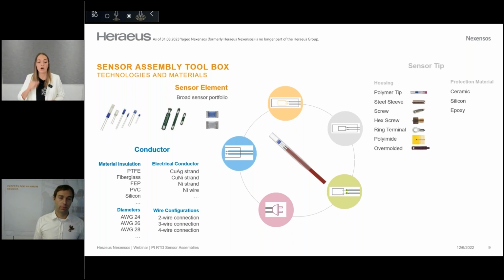Here you can see a selection of the conductor. Of course, our sensor is a passive component, therefore it needs to be energized, and therefore we're going to need a cable or a lead extension. So the conductor could vary in terms of material, in terms of the diameter, or for example the length. I don't want to go through all those materials, just let you know that of course we can react to customer requests and adapt the selection here. And we can also manufacture a 2, 3, and 4 wire connection.